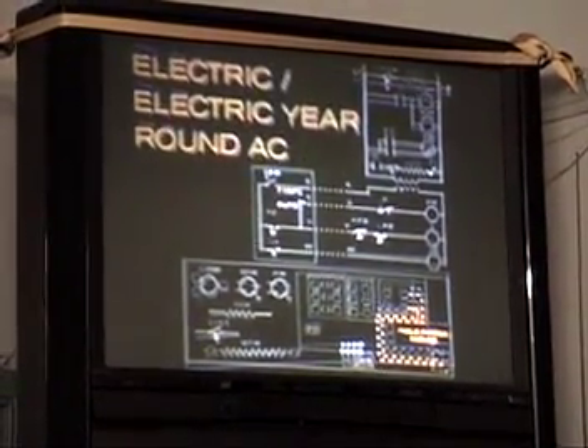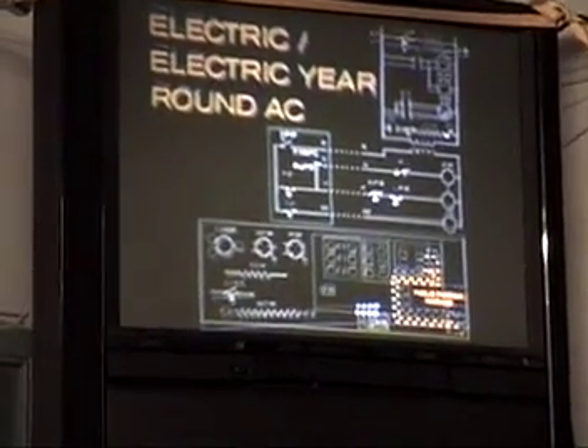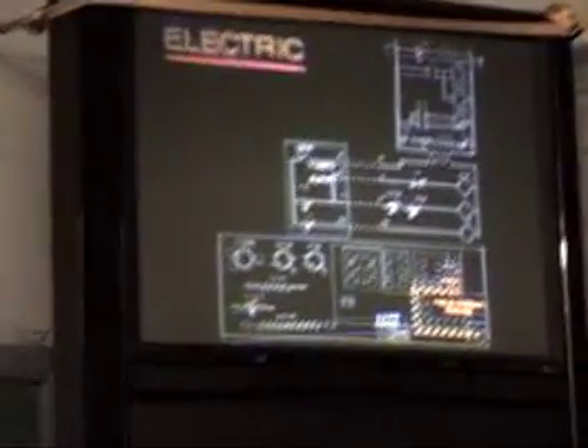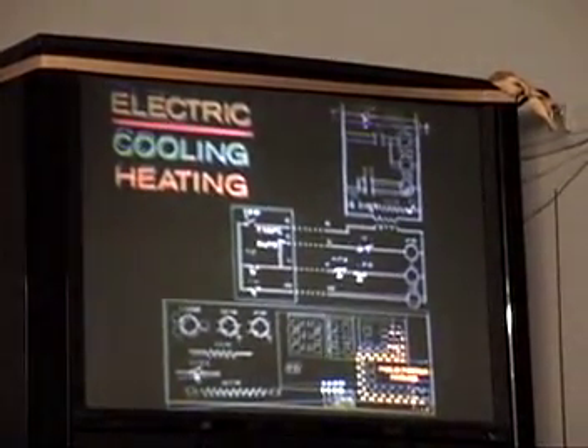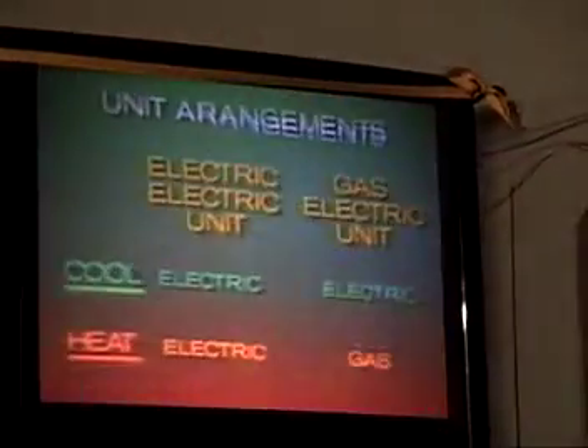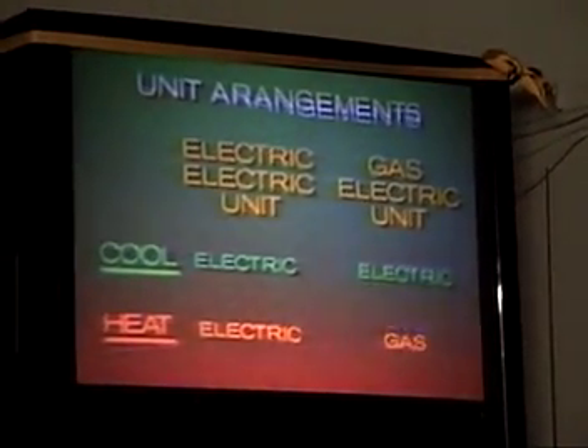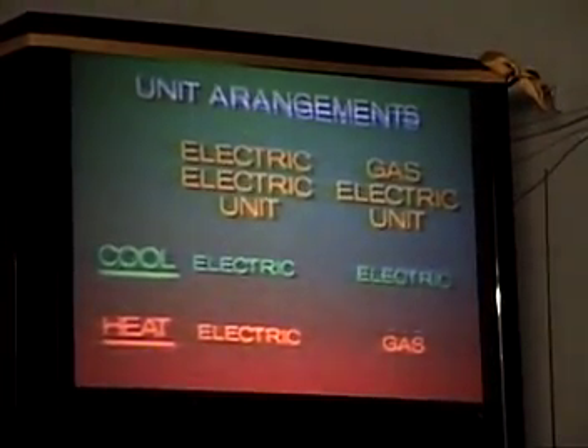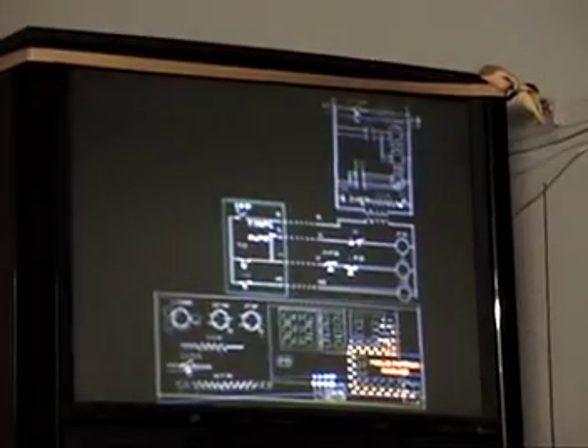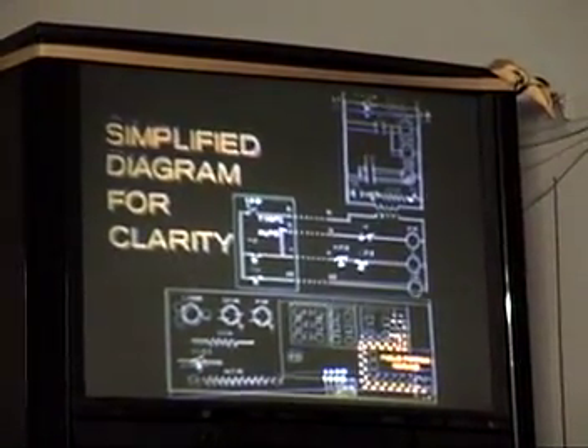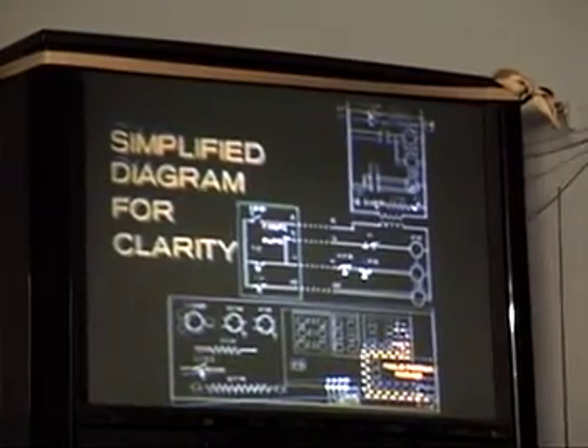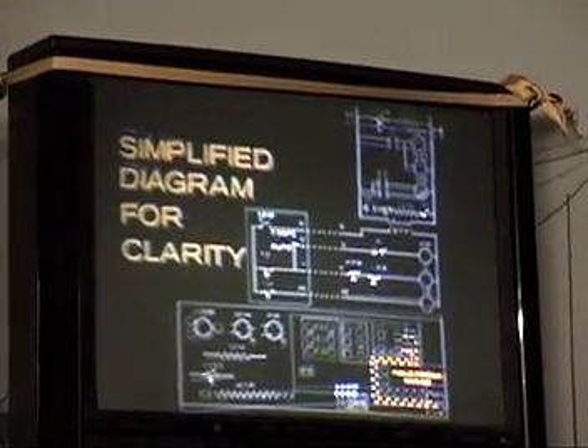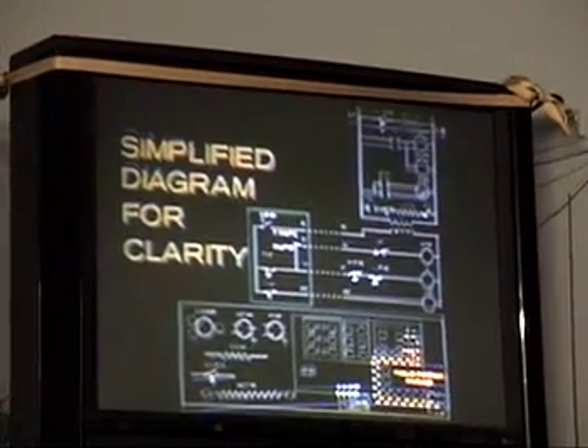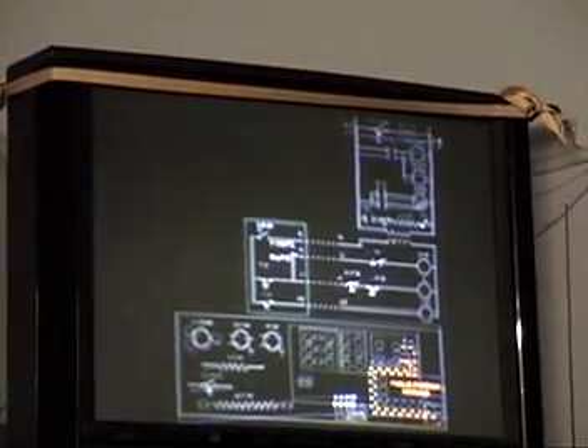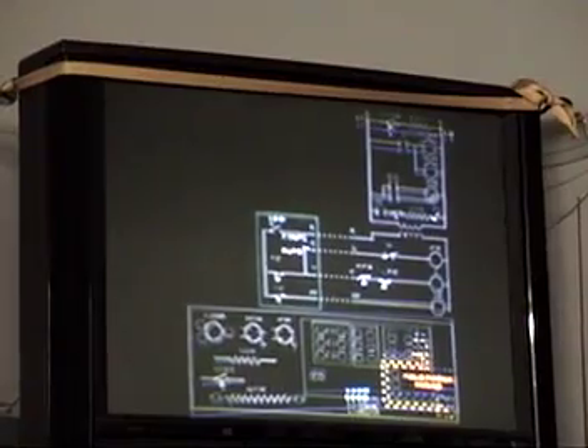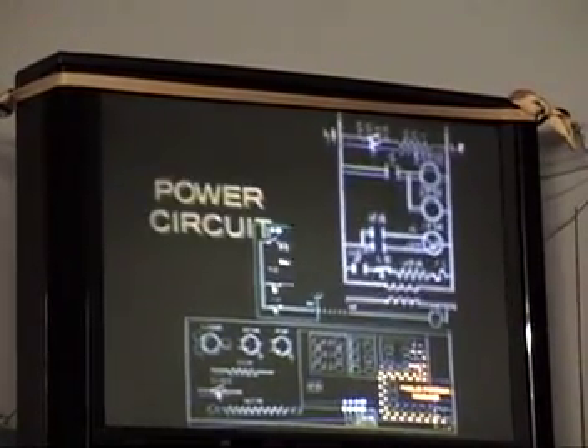This diagram shows a unit usually referred to as an electric year-round air conditioner. It has electric cooling and electric heating components. Later, we'll look at a gas-electric year-round air conditioner with a gas heating arrangement and electric cooling components. The wiring shown here is not for an actual unit, but it is typical, although simplified. In the interest of clarity, some protective devices and wiring have been eliminated so that the basic elements can be easily seen. Let's look at the wiring schematic and simplify it by breaking it down into 3 parts.